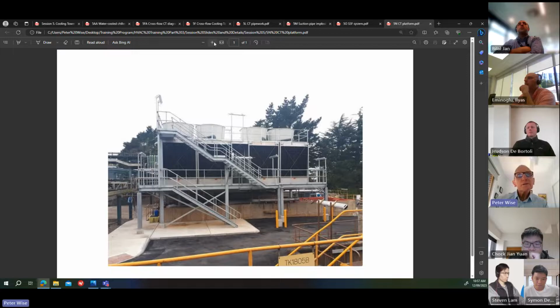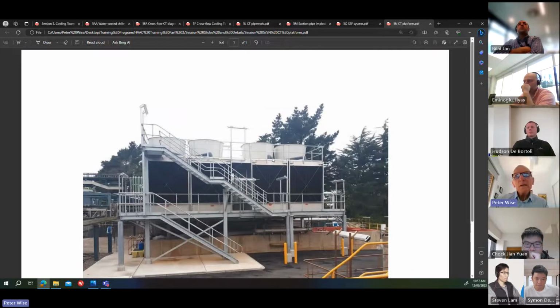You can see at the top here, you can just see these pipes coming out. So this is a cross-flow cooling tower. The fill takes up the entire side on both sides. The pipes, the return water pipes, the hot water pipes are coming up through the middle of the cooling tower and then distributing out to each what's called a cell of the cooling tower or to the fill. So there's a water distribution basin at the top of each of these cells. So you can see those pipes coming across to the water distribution. Yeah, so you need access to all those things. The water distribution basin may clog up with dirt. So you need to clean them out periodically as well.